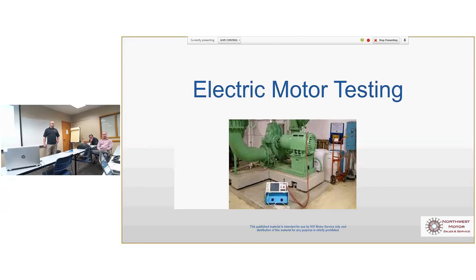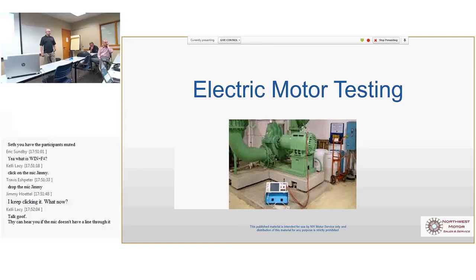the equipment rental would come into play. We will leave the online test equipment out at a customer site sometimes. So if we're trying to identify a problem that is kind of tough to pinpoint, we have a glass plant customer that we did this with most recently. A 200 horsepower motor just shut down sometimes, and there wasn't really any indication of what was going on. It was on an old soft start. Totally intermittent. And sometimes it would shut down.